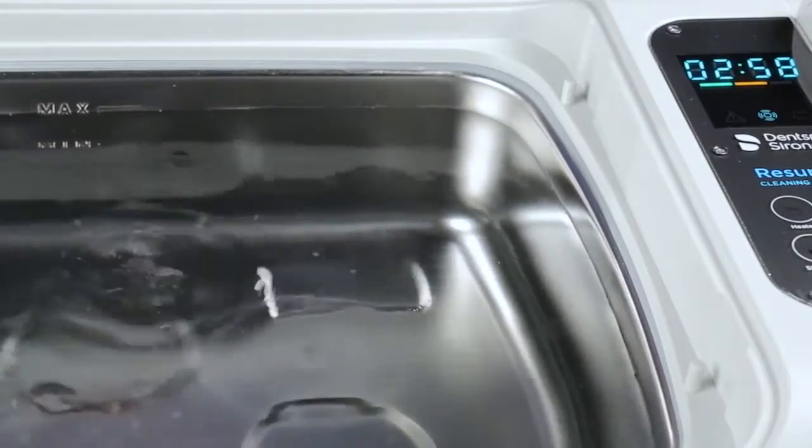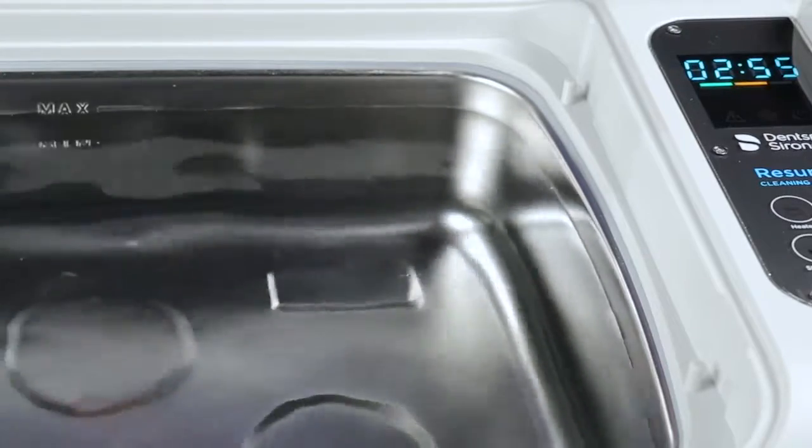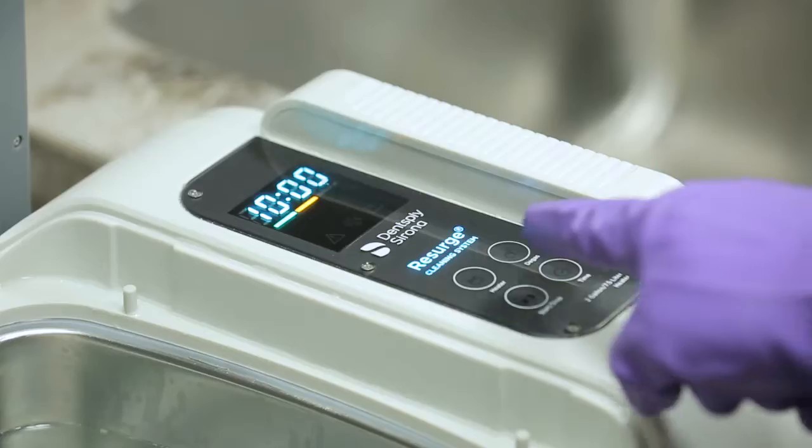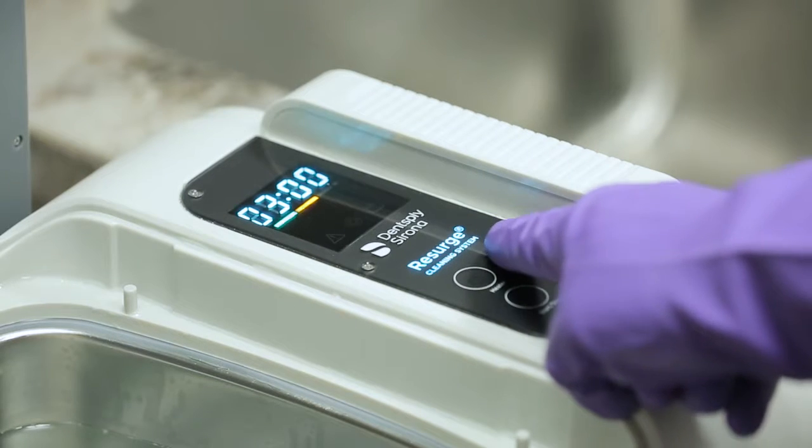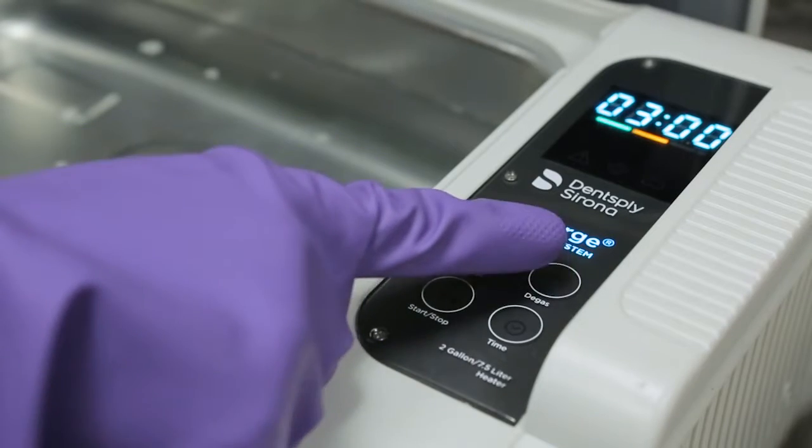Prior to using the bath for the first time during the day, it is critical that you degas the bath. The Resurge ultrasonic cleaner has a convenient degas cycle which runs for 3 minutes. Simply press the degas button twice.